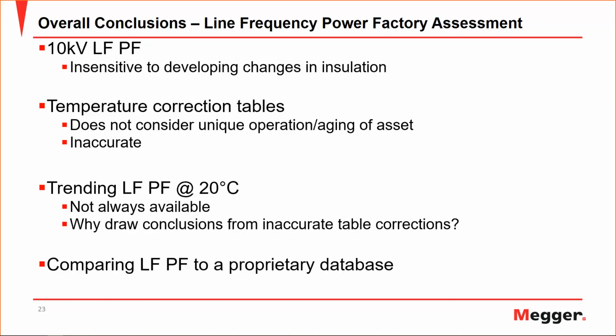So finally, what some people can do is compare line frequency power factor to a proprietary database, but unfortunately these have high membership costs. They're not readily available, and since they have been using 20 degrees C to do all their corrections, again, it is going to be inaccurate and not very suitable for getting the best insulation assessment that you can get. And that's where 1 hertz power factor comes in.